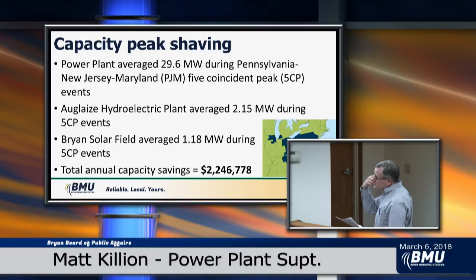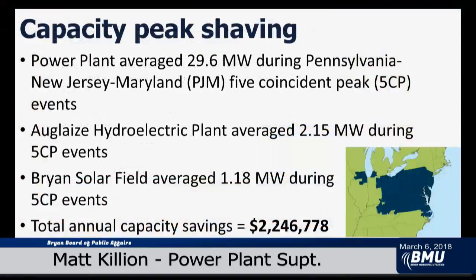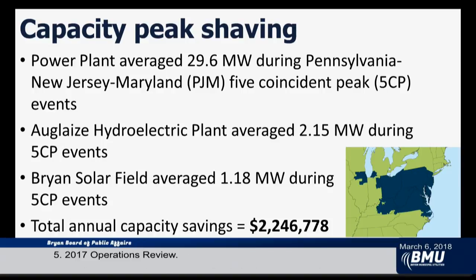The Auglaize is counted in that also. We only have so much water we can use down there, so we try to hold back and catch as many averages as we can. We got 2.1 megawatts out of Auglaize. The Bryan solar field was back up and running in the summer, so it helped us out at 1.18 megawatts during the 5 events. That's a total annual capacity savings of over $2.2 million just for the PJM portion. So that was a really good year for us there.